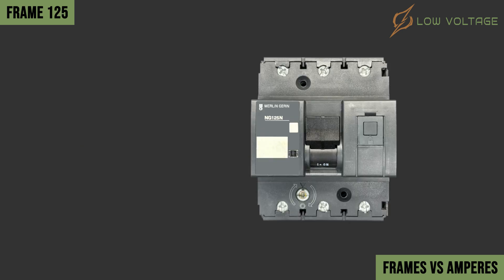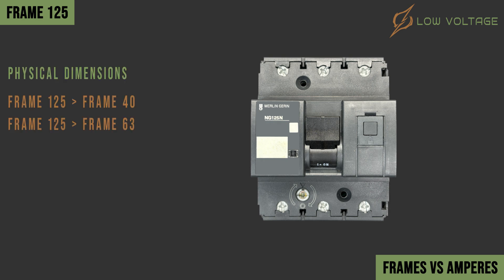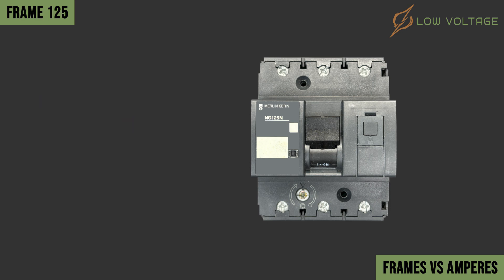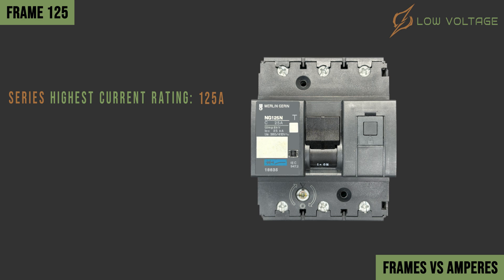The last frame in the MCB series is Frame 125. This frame has bigger physical dimensions than Frame 40 and Frame 63, because it can offer higher current ratings and characteristics. In this example, the series code is a designation for Frame 125, so the maximum series MCB rating is 125 amperes, and the current rating of this MCB is 25 amperes.